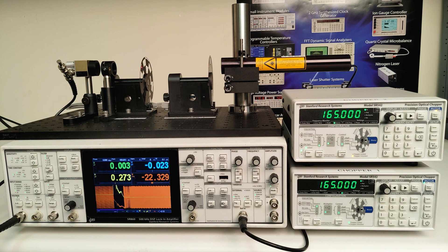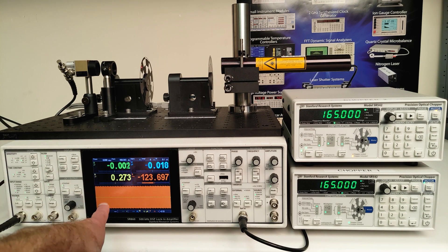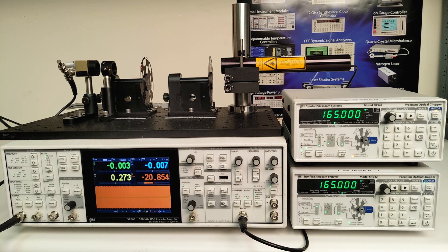I find it most useful to monitor X, Y, R, and theta on the lock-in front panel. In particular, R and theta will be used for the phase alignment procedure that follows. I also show R and theta on the strip chart history on the bottom.